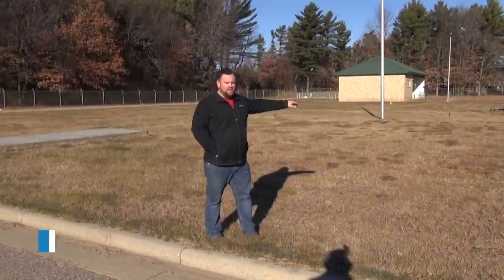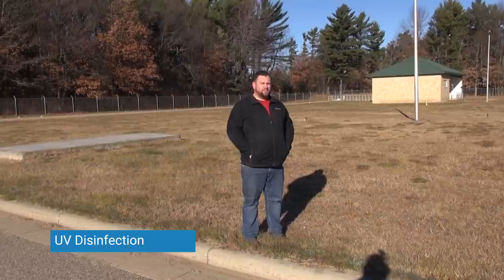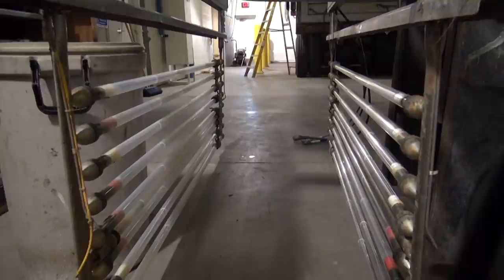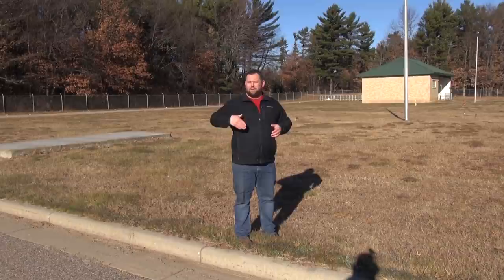The last stage of treatment before we send it to the Wisconsin River is housed in that building. It's not disinfection season right now so there's not much to see. Between May 1st and October 31st, we have an ultraviolet disinfection system — UV bulbs in big racks set down into the channel. The water is routed through a channel with about 190 UV disinfection bulbs disinfecting anything remaining. If bacteria get through the final clarifier, ultraviolet light kills and disinfects the water before it goes to the Wisconsin River, keeping it safe for boaters, fishermen, and swimmers.